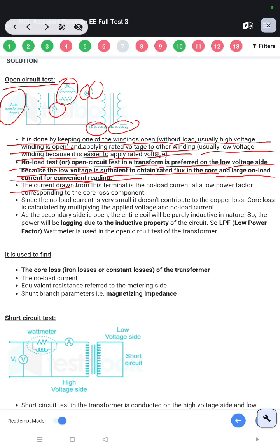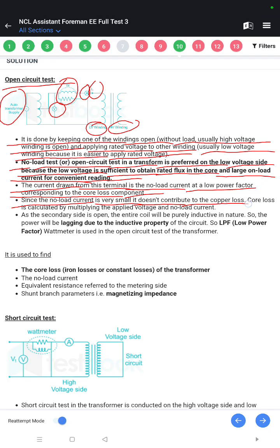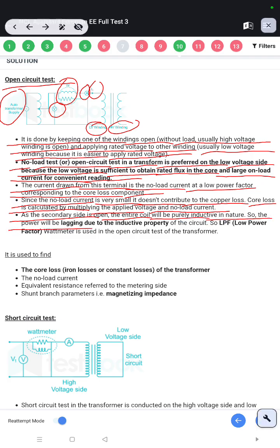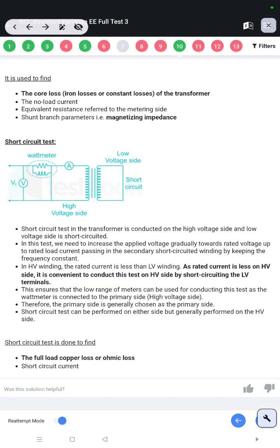The current drawn from this terminal is the no-load current at a low power factor, corresponding to the core loss component. Since the no-load current is very small, it does not contribute to the copper loss. Core loss is calculated by multiplying the applied voltage and no-load current. As the secondary side is open, the entire coil will be purely inductive in nature, so the power factor will be lagging due to the inductive property of the circuit. So, a low power factor wattmeter is used in the open circuit test of the transformer. It is used to find the core loss of the transformer.